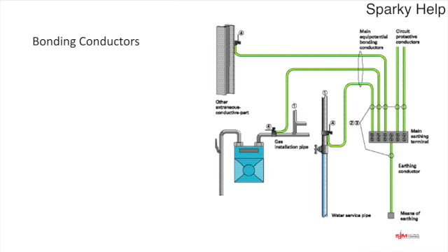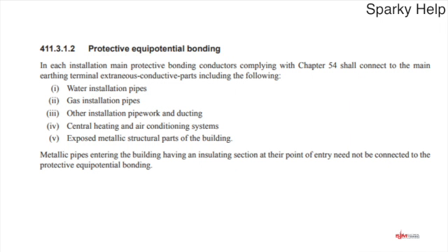Here's a little picture that just shows all that and the different locations that you can take them to. So there's the gas meter, there's a water pipe, which we will come back to, and showing where the connections are. So they're on your side of the stopcock, they're on your side of the meter before branch pipework. And if you have structural steel, then it's just a suitable location that you're going to take them to.